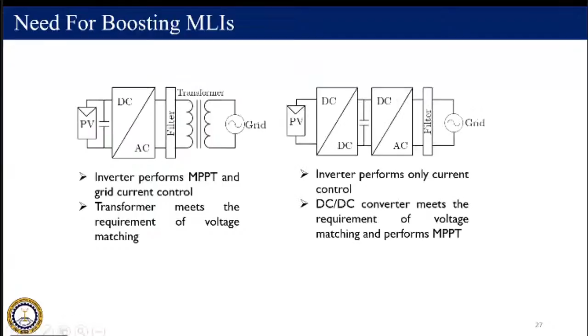The main reason for boosting inverters is that, because the PV voltage is very low, either we have to go for a transformer for boosting the voltage, or we have to go for a DC-DC converter. That is, either an AC boosting or a DC boosting. If you go for AC, we have to go for a transformer, so it is going to increase the size and it is bulky. If you go for DC, then you have an additional converter coming in, and it is a two-stage conversion. The efficiency will be lower.